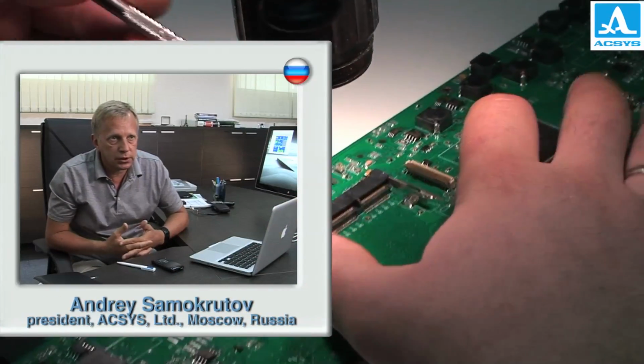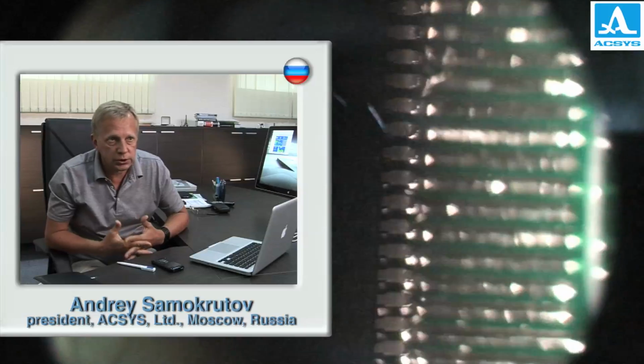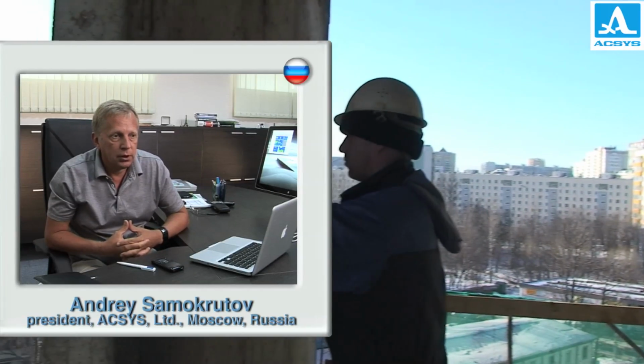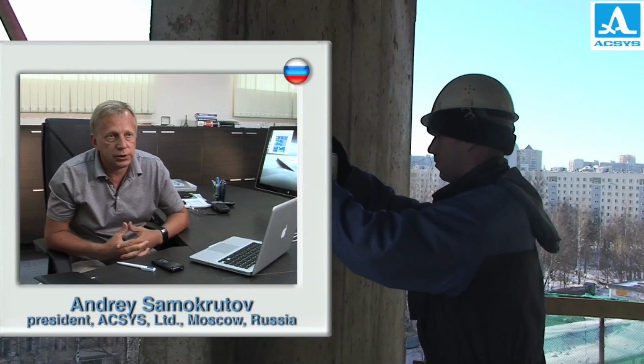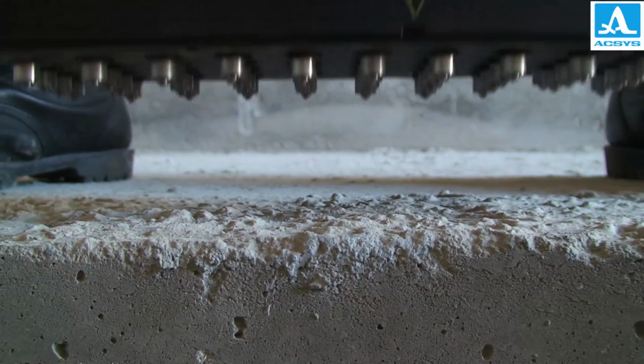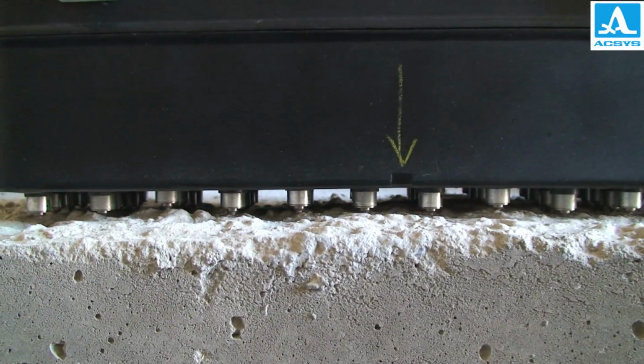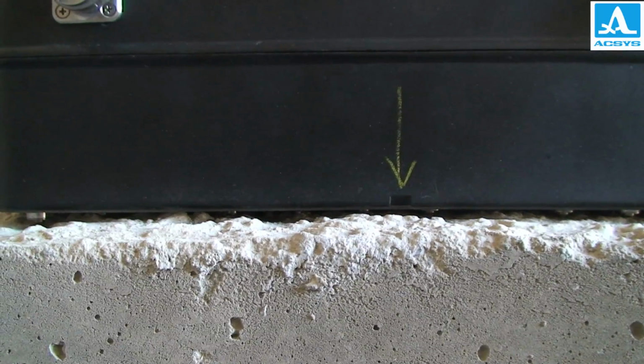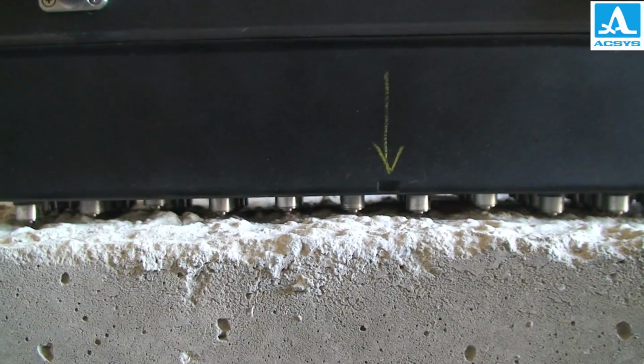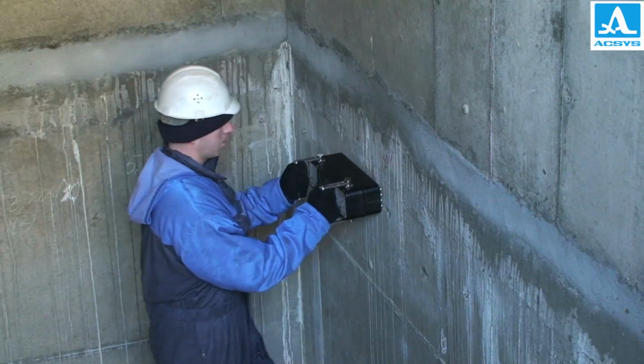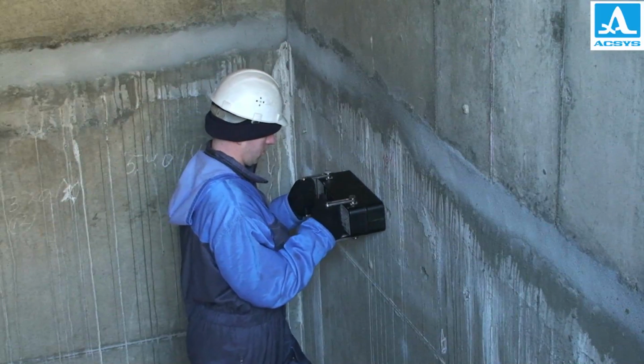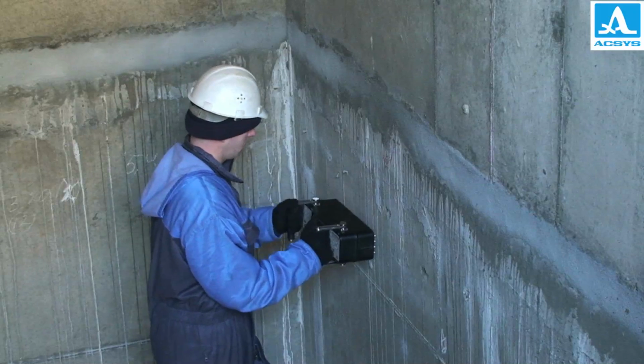Having resolved the problem of dry point contact and the problem of a contact agent required for testing, we have got a synergistic effect. The design philosophy of the antenna array granted one more important advantage. Since every transducer is equipped with an independent spring suspension, the ultramatrix array adapts to the relief of the object. You can work easily, even on coarse plates with roughness up to 1 centimeter. And the large area of the MIRA array allows the collection of data from the whole tested zone promptly.